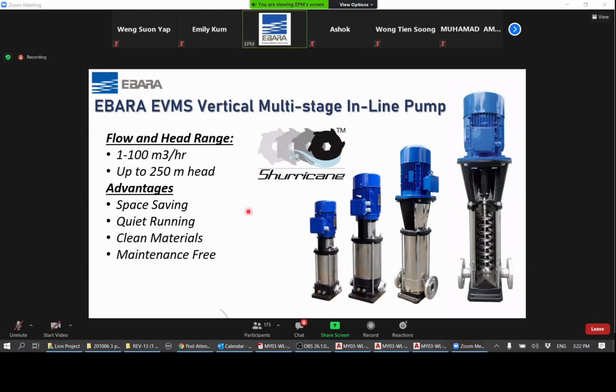Now, I mentioned some of the advantages of this pump. So space saving, you can see because of a vertical design, the pump takes very little floor space, and that's good for today's pump rooms, as many developers are squeezing pump room space to be very small. So this type of pump will be very ideal. Very quiet running because of the vertical design and the way it is constructed. It does not have any alignment issues.